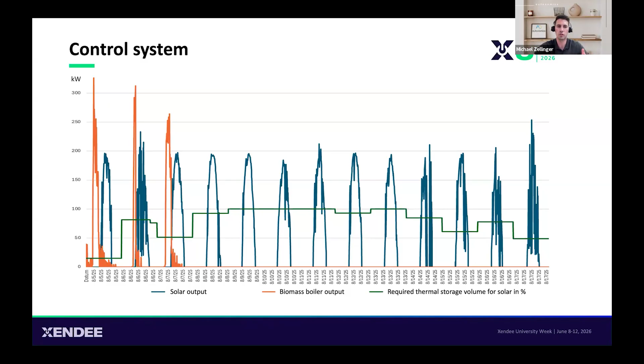Without forecasting, the boiler would fire up almost every morning, because the control system only sees the current storage temperature and reacts accordingly when a specific threshold is reached. The biomass boiler fills up the storage. With forecasting, the system knows that solar energy will be available within the next few hours, and the biomass boiler can safely wait. This avoids unnecessary boiler starts and allows the solar thermal system to cover a large share of heat demand in summertime.